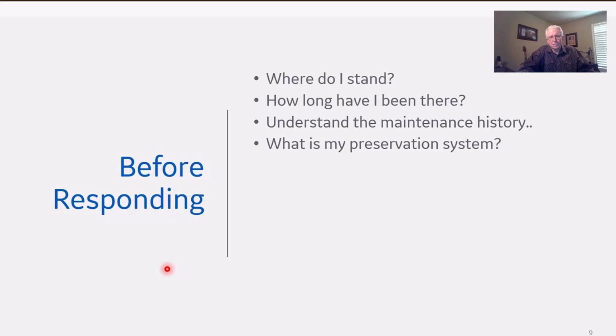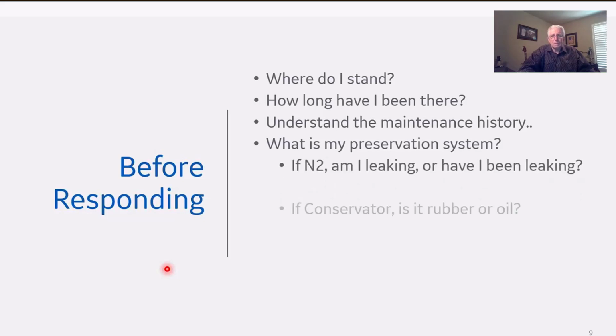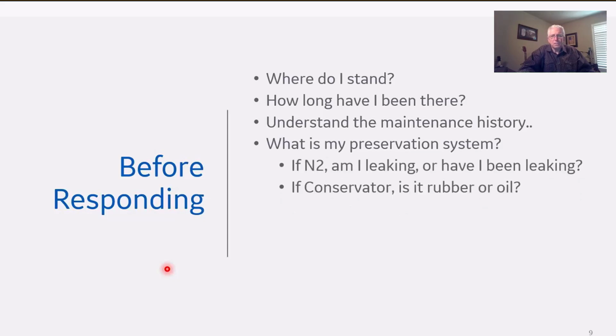So what's my preservation system? And if it is nitrogen, what's the frequency with which this nitrogen bottle has been replaced in that transformer? And if it's a conservator, you need to know if it's got a rubber bladder or if it's an oil conservator that breathes.